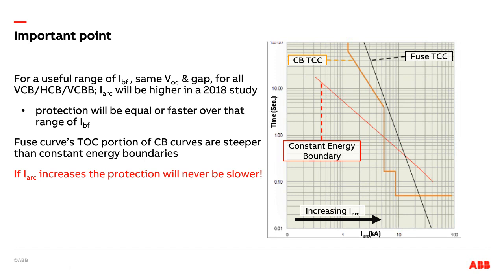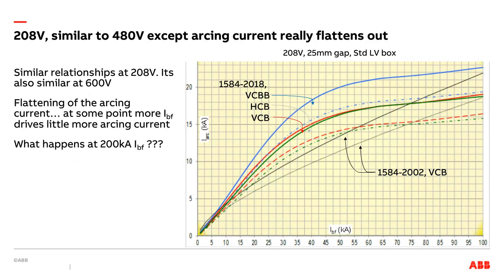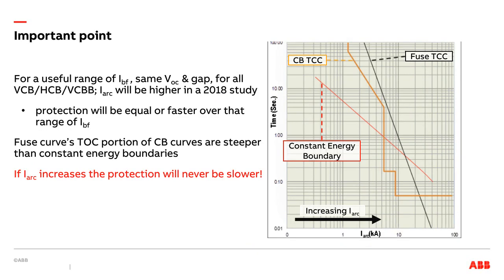So again, it goes back to the fact that current is higher, and when I plot that higher current on this graph, that value is going to be further to the right where it intersects this orange line or this black line. I am further down on the curve. This is time. My overcurrent protective device, breaker or fuse, will operate at the same speed or faster, never slower. Hopefully that was clear. Yes, hopefully that clears that up for that individual that asked the question. And let's move on to another.